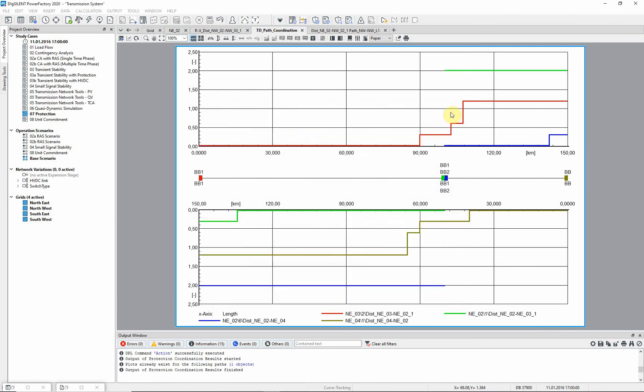The diagram changes due to the additional effects taken into account by the short circuit calculation. The reaches of zone 2 and 3 decrease due to an intermediate infeed and the starter times are displayed.